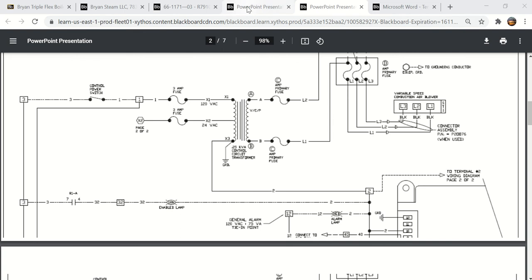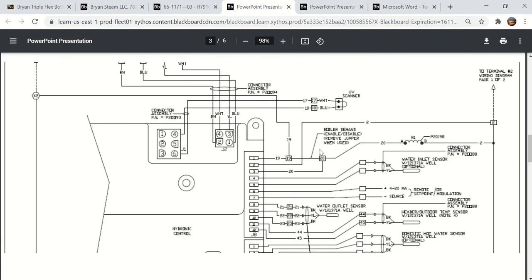And the reason I mentioned that, when we get back over here, when we were talking about this boiler enable disable, you would typically put a relay contact between 19 and 20 when you remove this jumper, and that would be called a dry contact, and the coil that controls this dry contact between 19 and 20 would actually be from your building automation system, because you wouldn't put 24 volts from your building automation system in with the 24 volts that's coming from the transformer in this boiler.